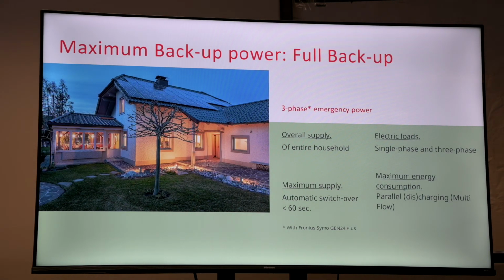Again, about the maximum power and the full backup on the Fronius Gen 24. So overall supply, you can do on the entire household itself. You're limited to 4 hours of backup generation power, as well as on the electric load, either single phase or 3-phase, all depending on what is available. And then the maximum changeover time. It is 60 seconds, but it has been brought down to 13 seconds on the changeover from battery operation to normal operation.